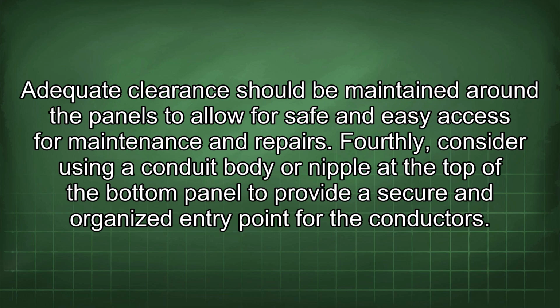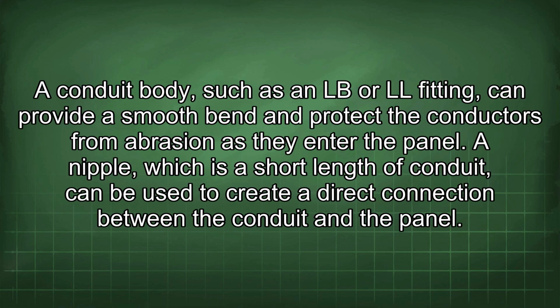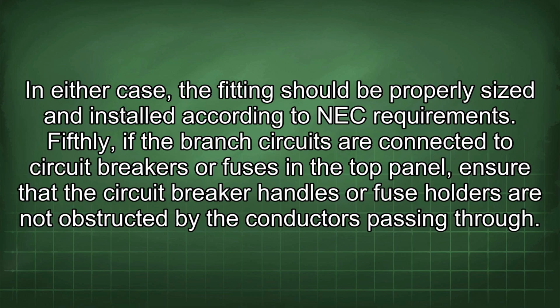Fourthly, consider using a conduit body or nipple at the top of the bottom panel to provide a secure and organized entry point for the conductors. A conduit body, such as an LB or LL fitting, can provide a smooth bend and protect the conductors from abrasion as they enter the panel. A nipple, which is a short length of conduit, can be used to create a direct connection between the conduit and the panel. In either case, the fitting should be properly sized and installed according to NEC requirements.